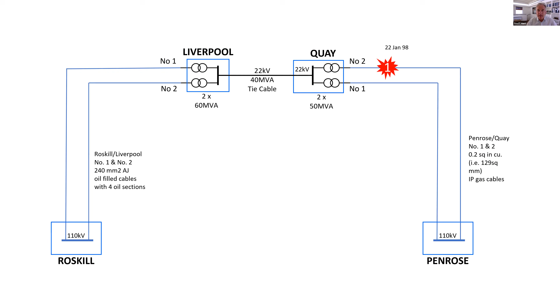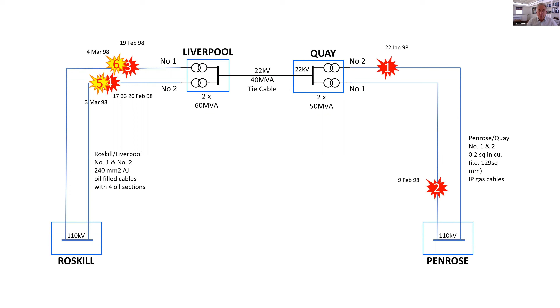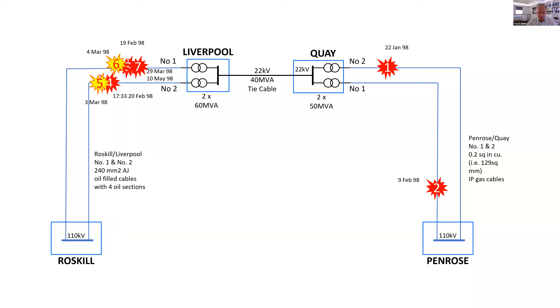There were attempts made to reliven two of the cables, shown in yellow in a minute. There they go. But the recovery was only short-lived. As I said, the actual failure mode turned out to be thermal expansion leading to mechanical failure at the joints. The subsequent inquiry was a little bit profound.